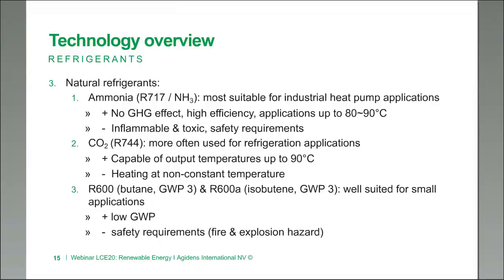An alternative to ammonia is CO2 itself, R744, which is used a lot in refrigeration applications and is also capable of output temperatures up to 90 degrees. The disadvantage in heating applications is that it doesn't heat at a constant temperature. Yet another alternative natural refrigerant is R600 or butane, with a global warming potential of just 3, and R600A isobutane, also with a GWP of 3. These are refrigerants well suited for small applications. The advantage is low global warming potential, but butane is very easy to catch fire and can even create an explosion hazard, requiring significant safety measures.